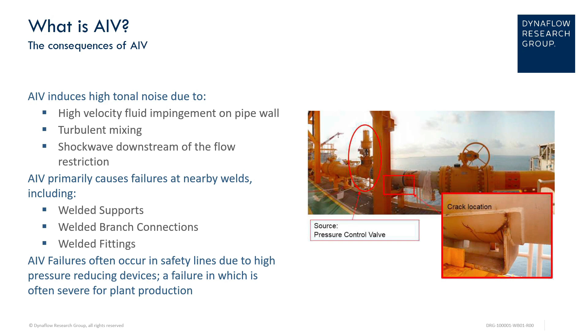The severity of AIV is a function of the pressure drop and gas mass flow rate passing through the flow restriction. Fatigue is commonly a problem at welded locations, and for that reason AIV primarily causes failure at nearby welds, including welded supports, branch connections, and other such fittings.